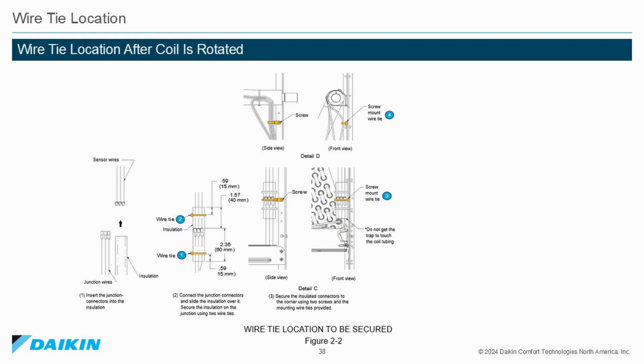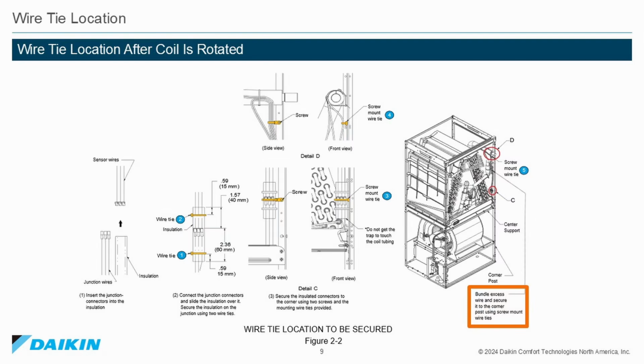Wire tie location after the coil has been rotated. See the diagrams below and in the installation operation manual for the location of the wire ties to hold cables in place. Insert the junction connectors into the insulation. Connect the junction connectors and slide the insulation over it. Secure the insulation on the junction using 2 wire ties. Secure the insulated connectors to the corner using 2 screws and the mounting wire ties provided. Bundle the excess wire and secure it to the corner post using screw mount wire ties.